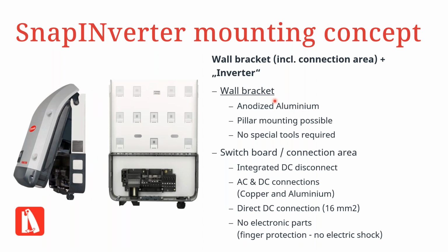The mounting bracket itself is quite handy because it comes in anodized aluminum. It can be used for either wall or pillar mounting. No special tools are required. Depending on whether it's a wall or pillar mounting, you would use the appropriate hole positions or a hole mounting kit accordingly. And then for the connection area, you have the integrated area for DC and AC connections, as well as the DC disconnect, which you can see here to the left.